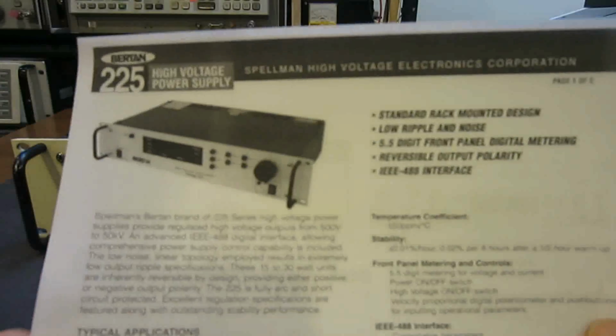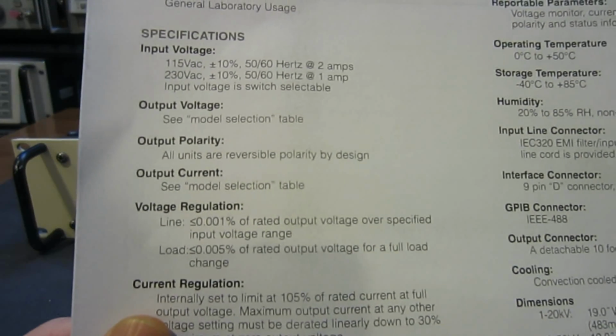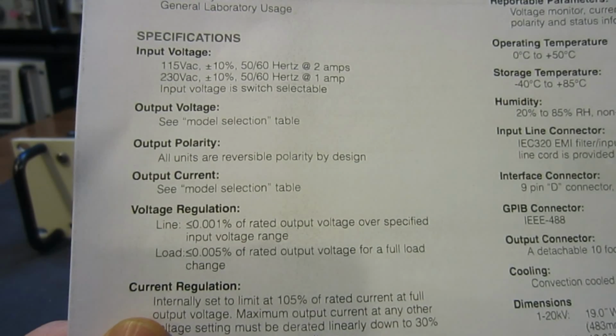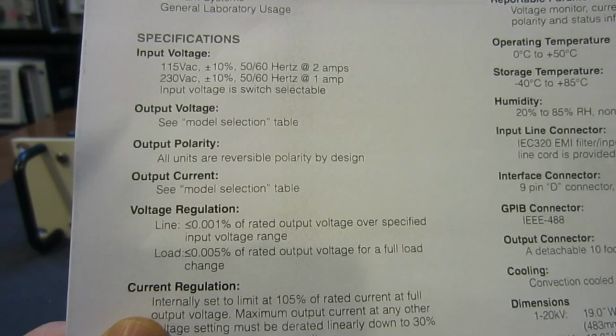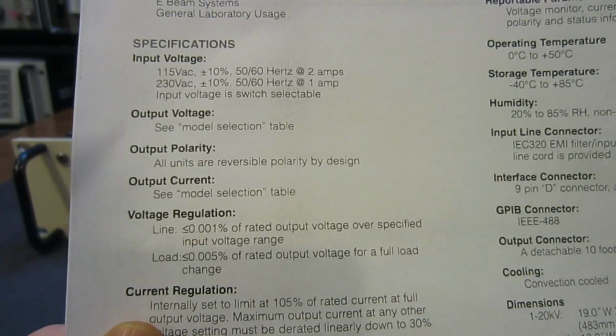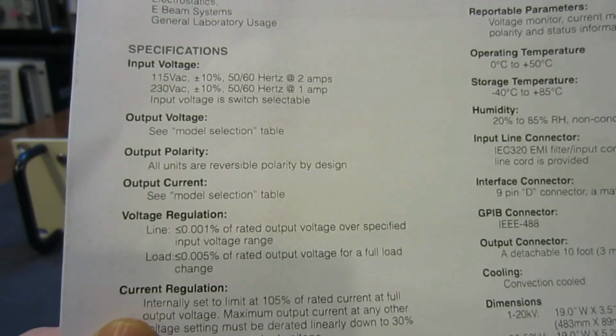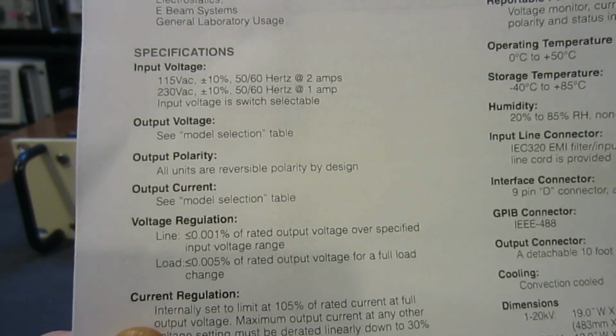And here I have the printouts for this series. And if you take a look, the voltage regulation is less than 0.001%, which is quite good. It's only about 10 ppm. And the load regulation is also very good. It's roughly 50 ppm of the full load.